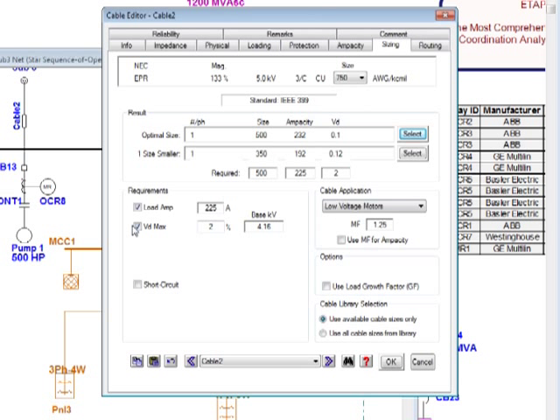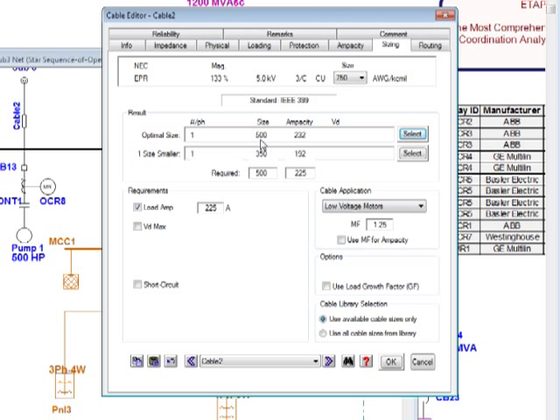My load current here is 225 amps. Using IEEE 399 for this particular conductor and installation, the program says I need at least 225 amps. The first size it finds is 500 kcmil, which gives 232 amps. The next smaller size, 350 kcmil, cannot satisfy this requirement, so I select 500 kcmil.